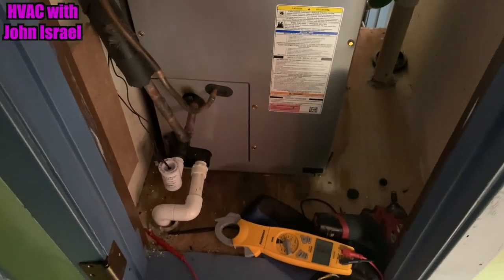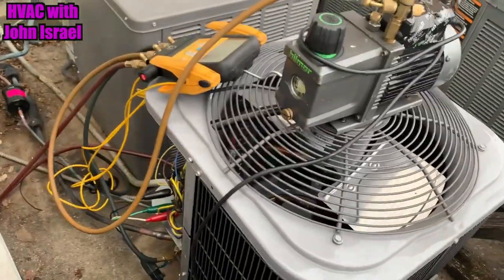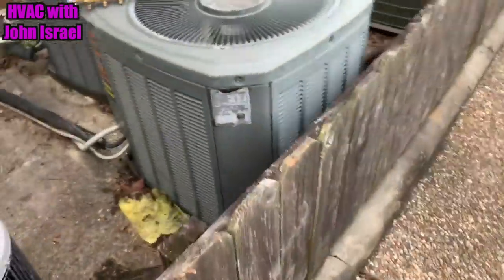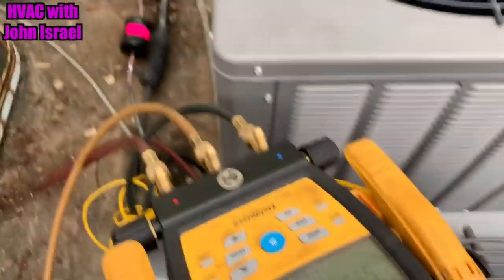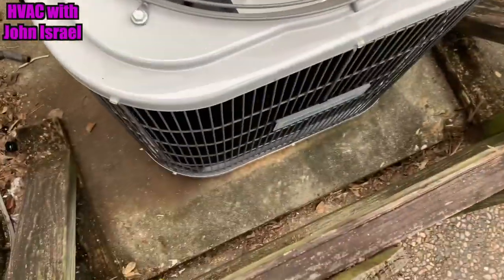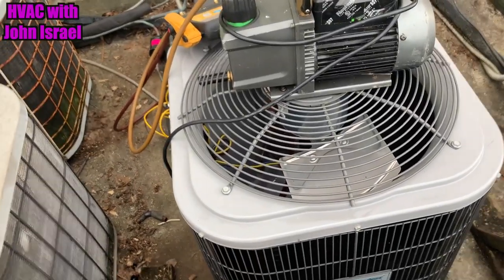Got the system in a vacuum right now. Here's the little Comfort Maker in a vacuum — new dryer back there. Let's see what the micron gauge says: 700 microns, 720-something. We'll let her pull a little while longer, get it down to 500. I will have my Appion hose and regular micron gauge again before summer gets here.